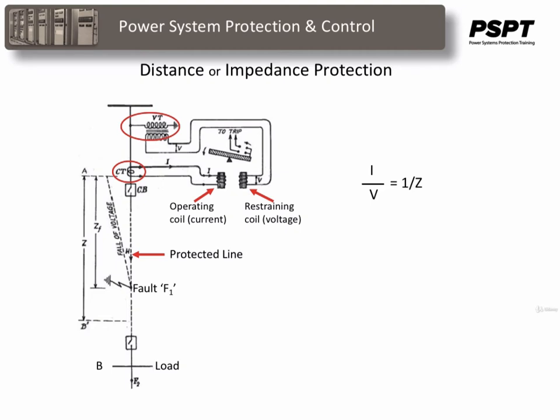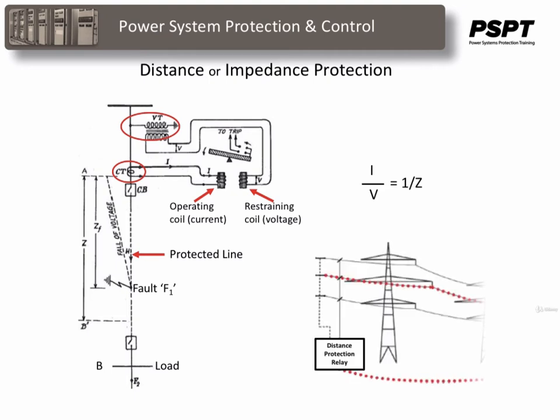The closer to the station the fault is, the less line impedance, the higher the fault current, and the greater the operating torque on the relay. Assuming that the impedance of the line is uniform, the impedance measured to the fault is proportional to the distance to the fault. Hence, such protection is called impedance protection or distance protection.